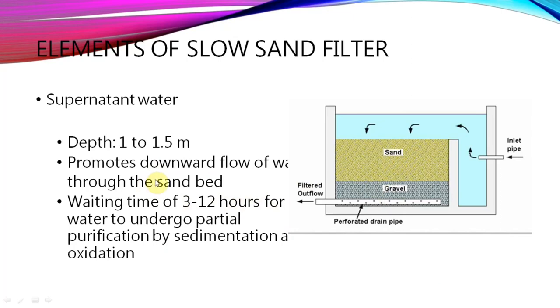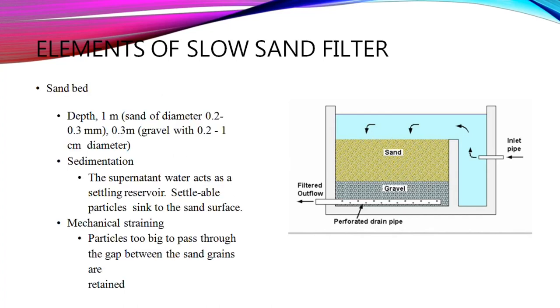Water is always directed downward, with a waiting time of 3 to 12 hours for water to undergo partial purification by sedimentation and oxidation. In the sand bed, sedimentation and mechanical straining occur: the supernatant water acts as a settling reservoir, settleable particles sink to the sand surface, and particles too large to pass through the gaps between sand grains are retained.